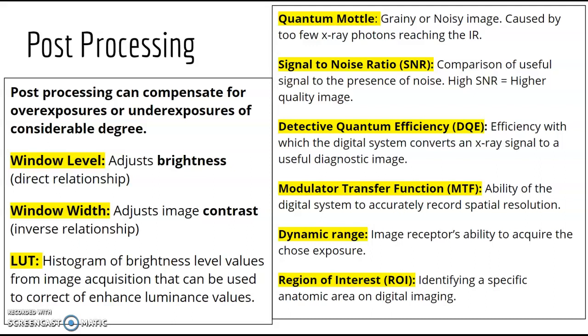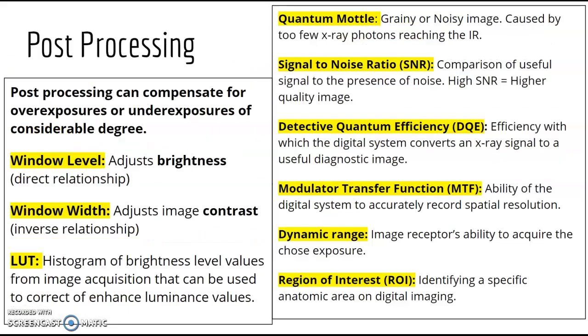DQE is your system's efficiency — how efficiently it takes an x-ray signal and uses it for a diagnostic image. Modulation transfer function is the system's ability to accurately record spatial resolution. Dynamic range is the receptor's ability to acquire a wide range of exposures — you can use a wider range of techniques on a chest x-ray versus a hand x-ray. Region of interest (ROI) is identifying a specific anatomic area on a digital image, such as using the ROI on a portable machine to get a better look at line placement.